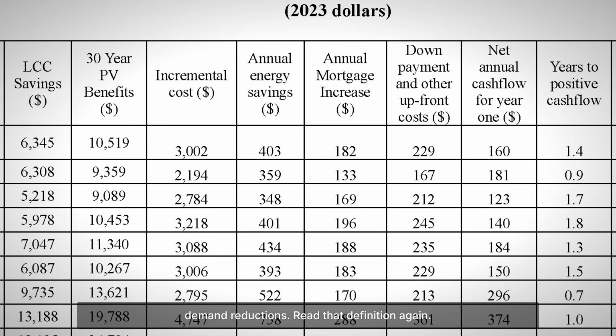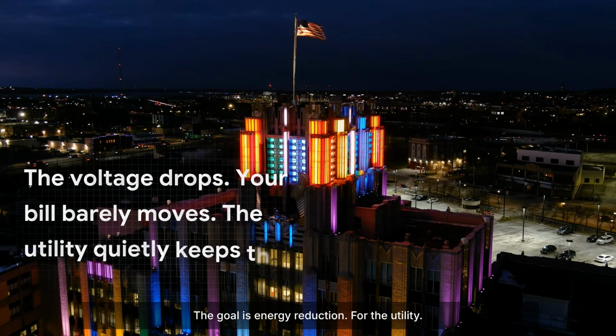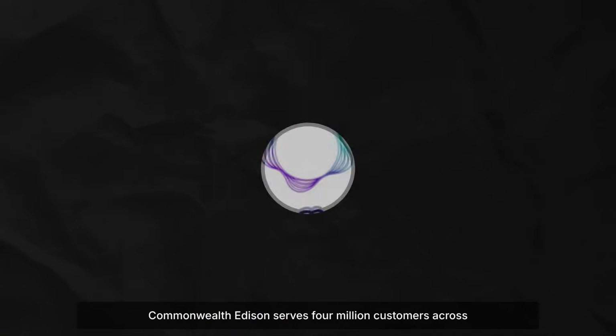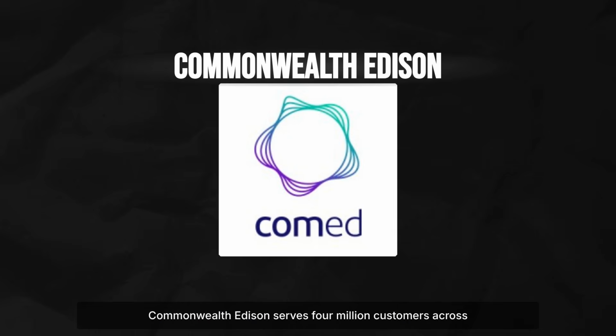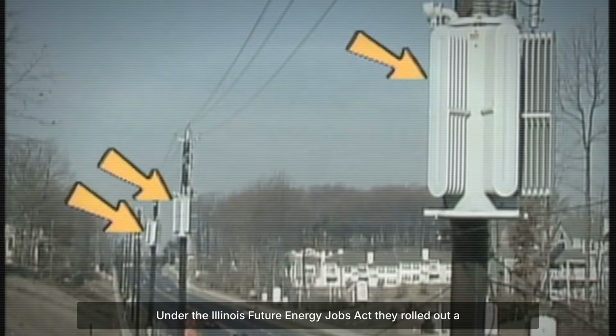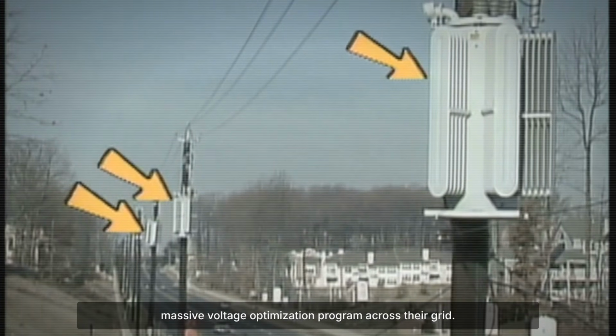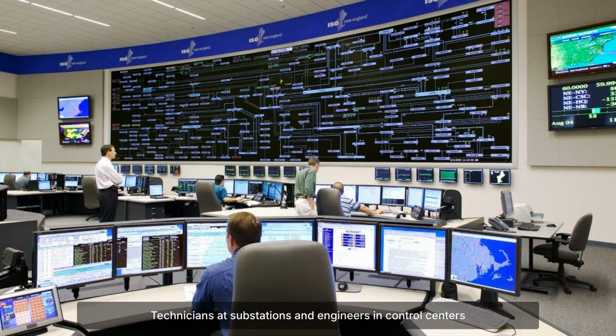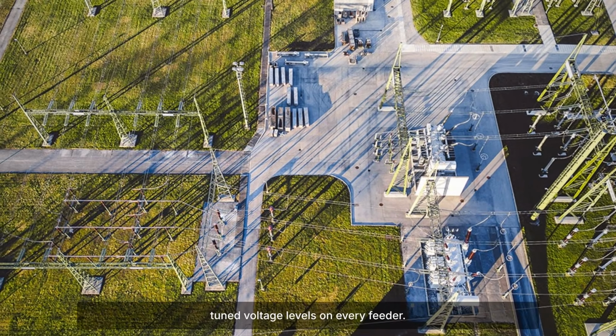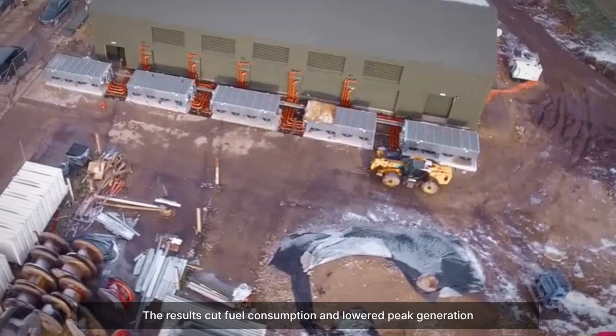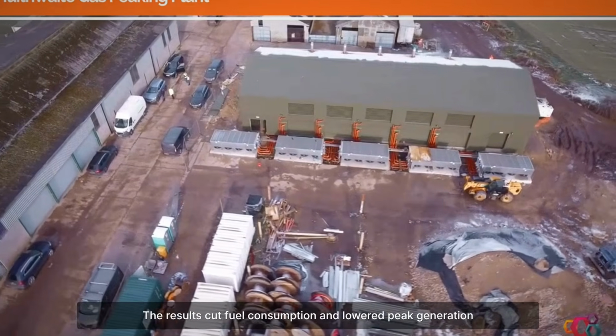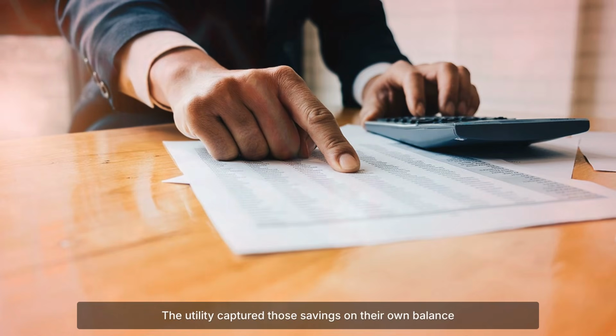Read that definition again. The goal is energy reduction for the utility. Commonwealth Edison serves 4 million customers across northern Illinois. Under the Illinois Future Energy Jobs Act, they rolled out a massive voltage optimization program across their grid. Technicians at substations and engineers in control centers tuned voltage levels on every feeder. The results cut fuel consumption and lowered peak generation demand. The utility captured those savings on their own balance sheets.